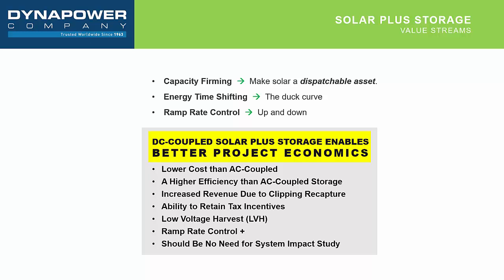Also, because the storage in the DC coupled configuration is parked behind a unidirectional PV inverter, there's no chance of charging storage from the grid, rather than from the array, and therefore there's no chance of clawback on the ITC. Low voltage harvest is another revenue pickup that we'll talk about, as well as ramp rate control plus. And interestingly, if you are doing a DC coupled system, whether for a greenfield or for a retrofit, there should be no need for an additional system impact study based on the addition of storage. That is to say, there are no changes to the AC characteristics of your PV array when you add a DC coupled storage system behind it.